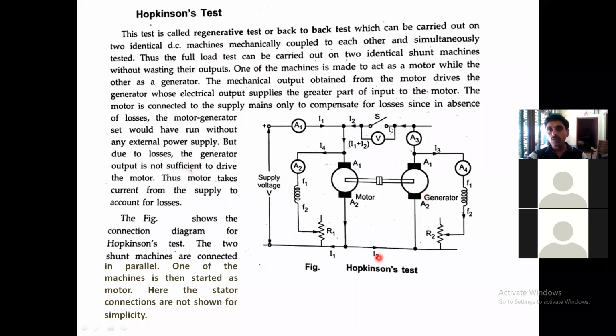After ensuring that only, we have to close the switch. Otherwise, because of the voltage difference between these two machines, there is a circulating current in this loop. So that's why till that point the switch is open. When the voltmeter reads 0, the excitation is adjusted such that the voltage across the generator is equal to the supply voltage. Then the switch is closed. So this is the starting point.